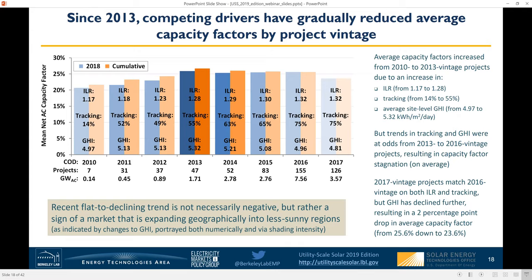This graph breaks out average capacity factor by project vintage or commercial operation date. There's a steady improvement from 2010 through 2013 vintage projects, driven by increases in all three metrics: average insolation as expressed by GHI, the prevalence of tracking, and the average inverter loading ratio. Since 2013, average ILRs have held more or less steady at around 1.3, while the prevalence of tracking and average GHI have moved in opposite directions, resulting in largely stagnant capacity factors among more recent project vintages. The lower average GHI since 2013 reflects the geographic expansion of the market outside California and the southwest — which is actually a positive trend, even though it has a negative impact on average fleet-wide capacity factor.